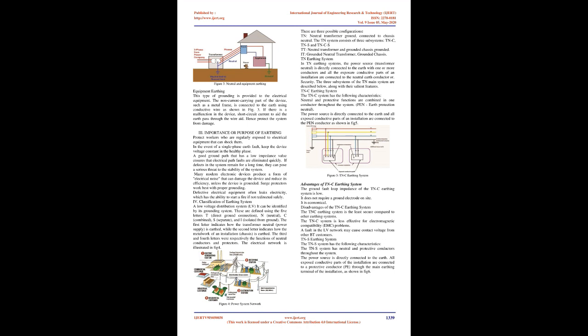Advantages of TN-C earthing system. The ground fault loop impedance of the TN-C earthing system is low. It does not require a ground electrode on site. It is economical. Disadvantages of the TN-C earthing system. The TN-C earthing system is the least secure compared to other earthing systems. The TN-C system is less effective for electromagnetic compatibility, EMC, problems. A fault in the LV network may cause contact voltage from other LV customers.